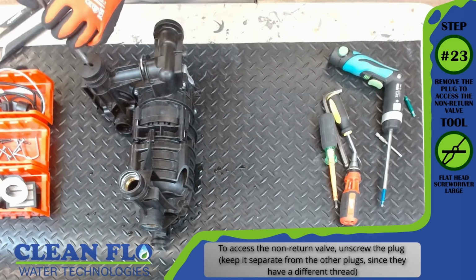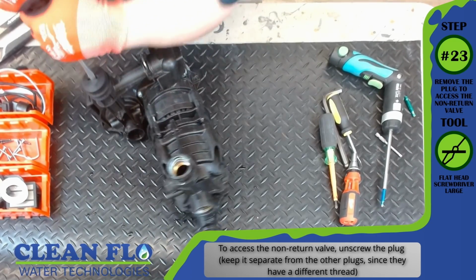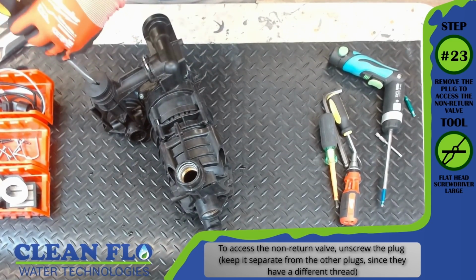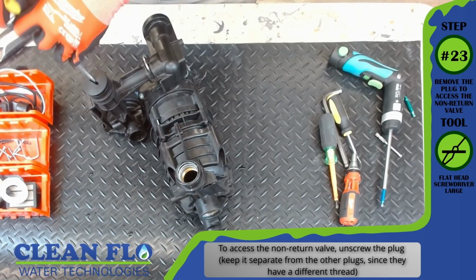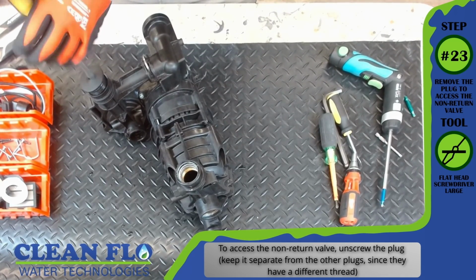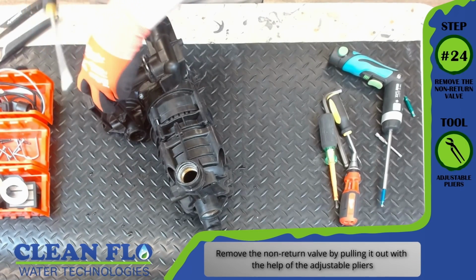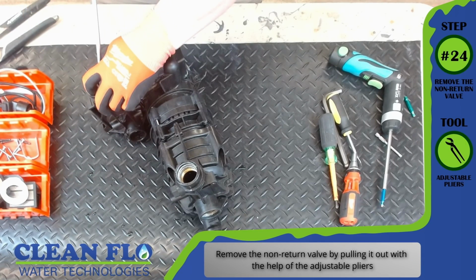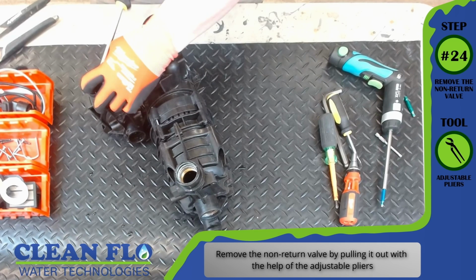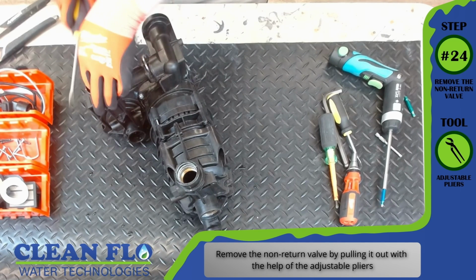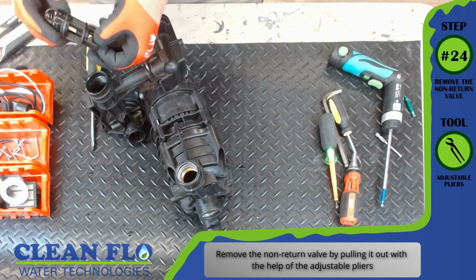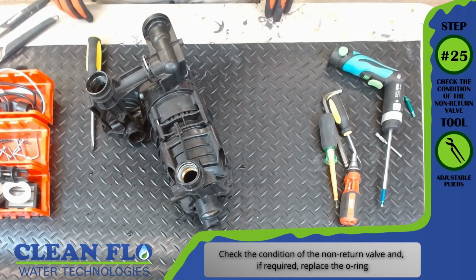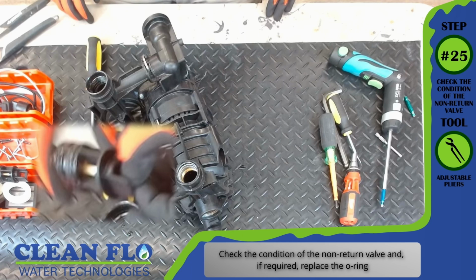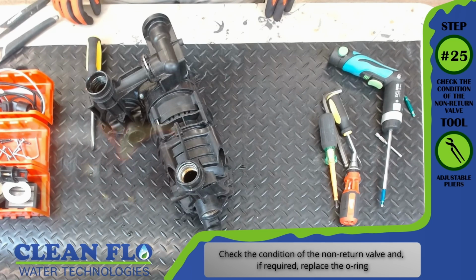The non-return valve is actually hidden inside the pump body and has an access panel on the front of the pump when it's assembled. Step 24, remove the non-return valve. Tool, adjustable pliers. Remove the non-return valve by pulling it out with the help of the adjustable pliers. Step 25. Check the condition of the non-return valve. Tool, adjustable pliers. Check the condition of the non-return valve, and if required, replace the O-ring.